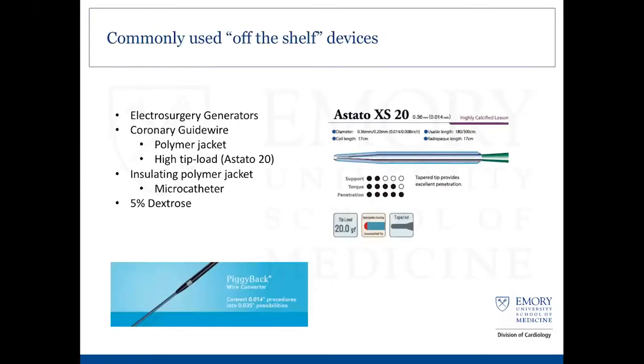These are the tools that are somewhat germane to transcatheter electrosurgery. First and foremost, you need an electrosurgery generator, a coronary guide wire that's modified. The ideal coronary guide wire is a polymer jacketed wire, because that polymer jacket has insulating properties, and then a wire that has a high tip load, because you're using this wire to push through target tissues, and that gives you some more pushability, much like the CTO space. So actually CTO wires are what are used. The common wire is the Astato 20 gram. This isn't the only wire that can electrify, but it is the most commonly used.